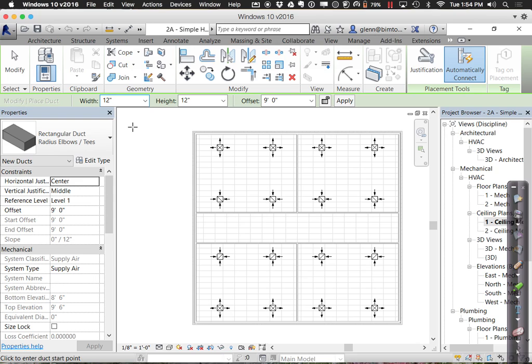At nine feet, you choose a type — whether it's supply or return. I'm going to run one set at nine feet and another at ten feet, ten foot six, or even eleven feet, depending on how much space you have. Now, regarding the height given — there's a vertical justification relative to it. So if it's vertical and set to nine feet with a twelve-inch duct, it'll go from eight foot six to nine foot six, centered on that nine feet. We also have horizontal justification: as I draw a line, is it going to be centered on that line or on one side or the other?